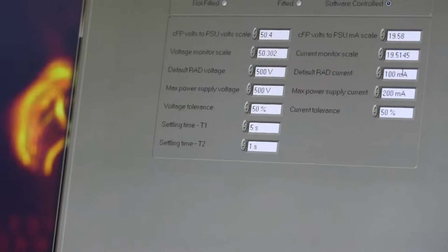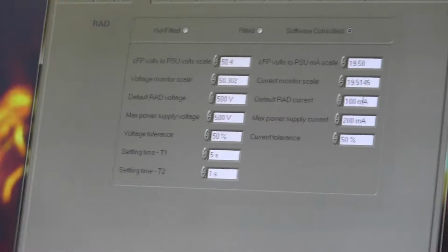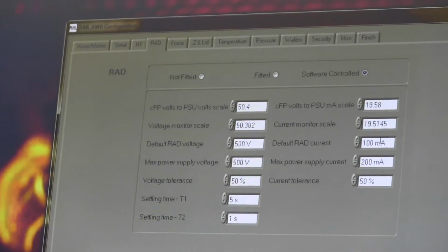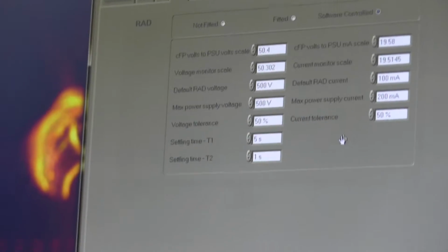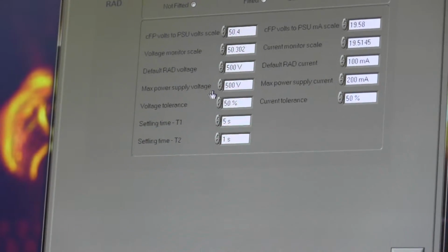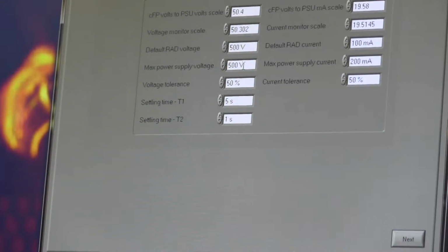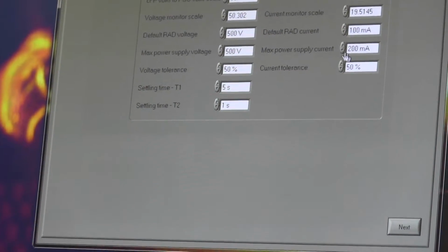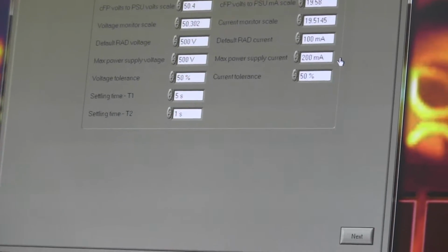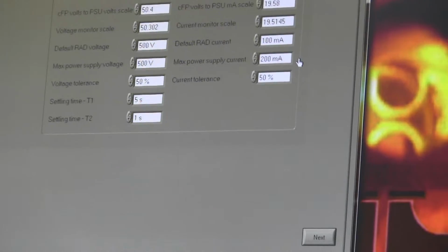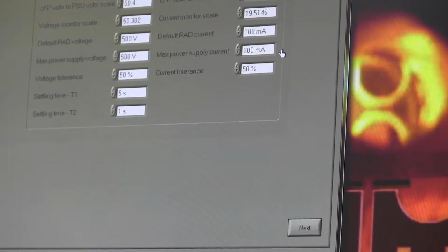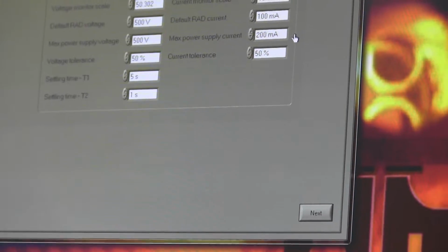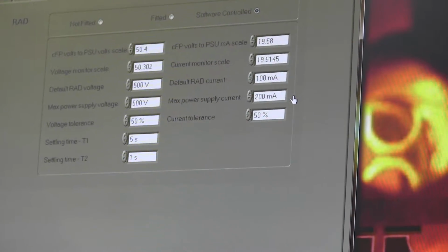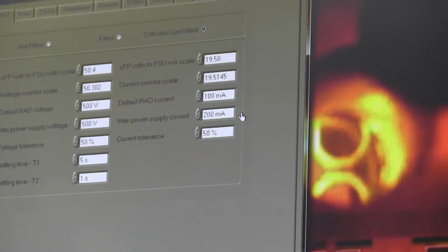The default voltage for this system is 500 volts, and the default current is 100 milliamps. All that means is that when you go into the program, those values will already be put there for you. So essentially all you need to do is turn the system on and off. But you can adjust it if you want from inside the software. You don't need to adjust the defaults. Maximum power supply voltage is 500 volts. Maximum power supply current is 200 milliamps. So if for some reason, in the event of a voltage breakdown, say, the software detects more than 200 milliamps, it will shut down the power supply to prevent any damage to it, because that's the specification that Spellman give us as the maximum that it can output.